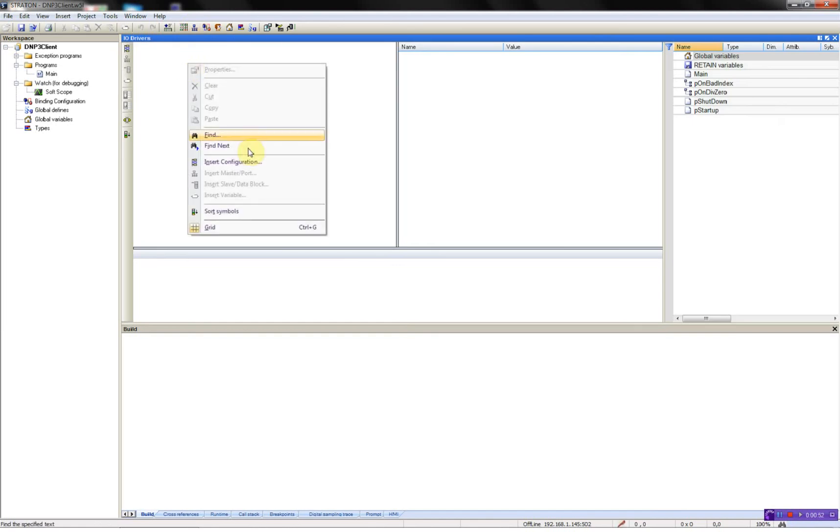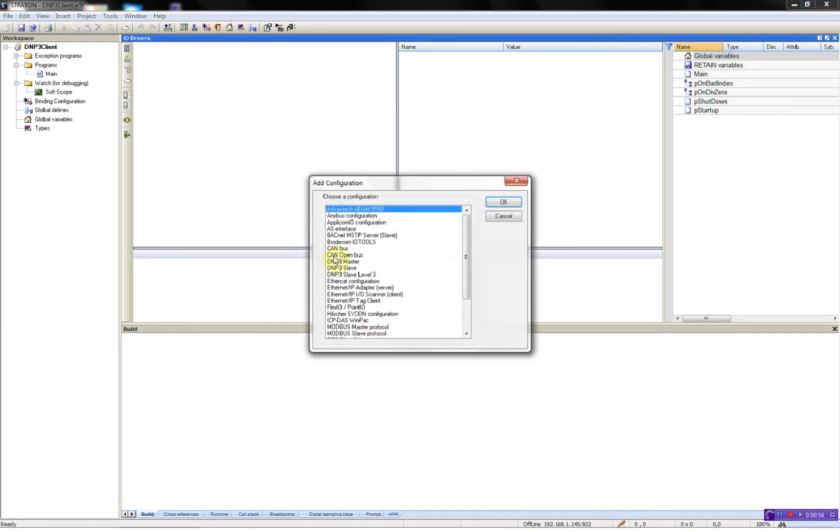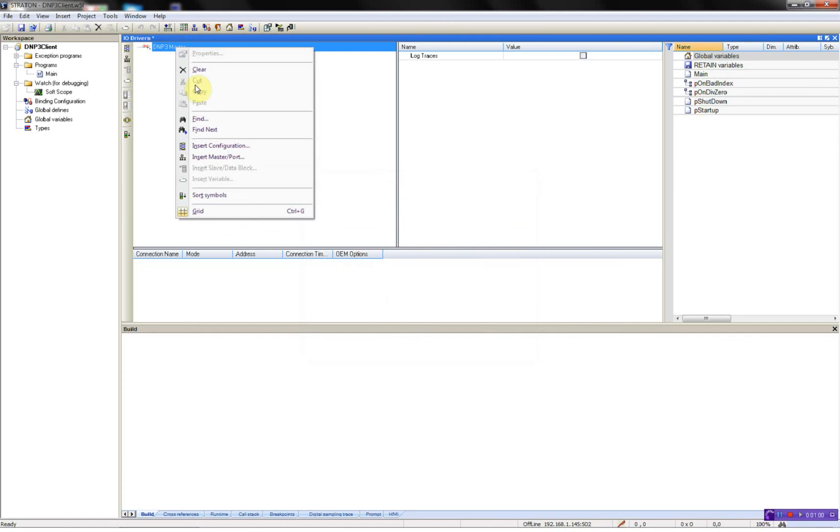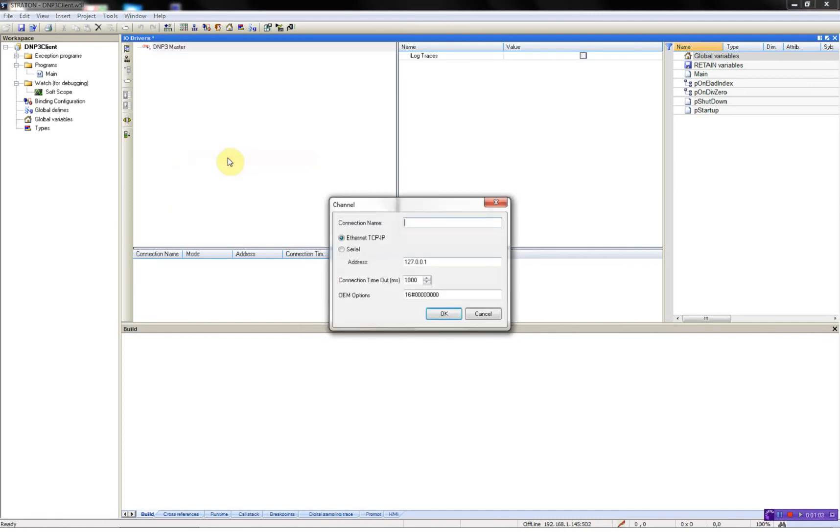In order to add the DNP3 client, I will open the Fieldbus Configurator, then right click Insert Configuration, then I will find my DNP3 master. Insert master port, Ethernet and then I have to type in the IP address of the DNP3 server.